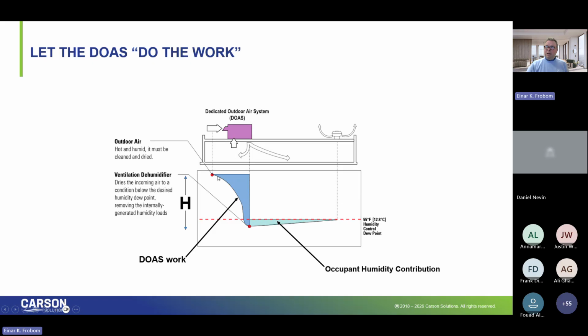And then this blue keel shaped line represents a decrease in humidity as it goes through possibly an energy recovery device, but then a mechanical cooling. And ultimately, you've got this low point indicated here. And what that's indicating is don't just have your DOAS unit stop at 55 degrees and saturated, because that's the typical control point of most rooms. So in order to handle the occupant level of moisture, dig a little deeper, go down to about 48 to 50 degree dew point off your mechanical cooling coil, and most mechanical-based DOAS units can easily attain that level. Now you have the sponge effect to absorb the moisture contribution of the people.